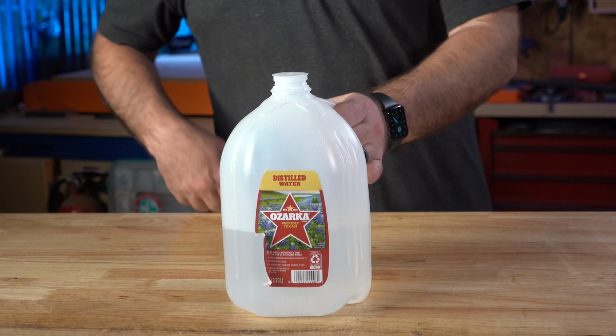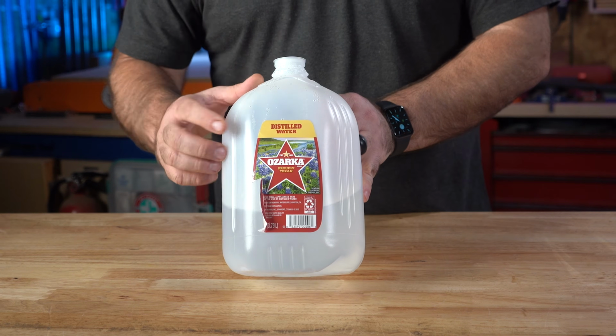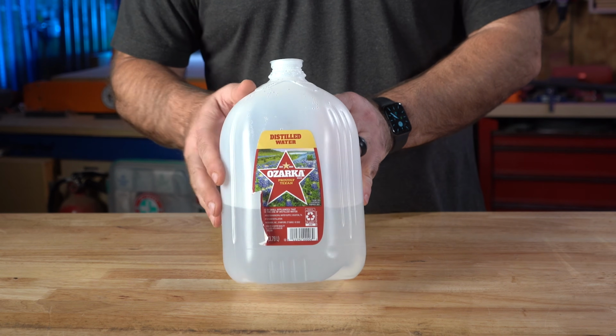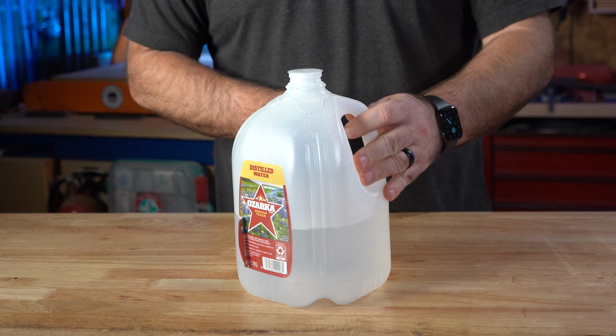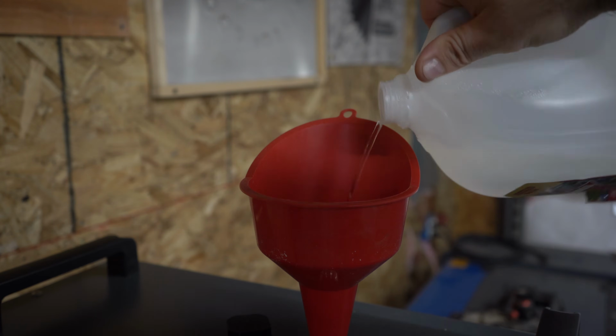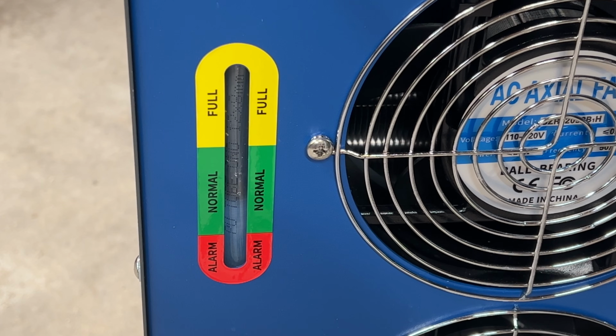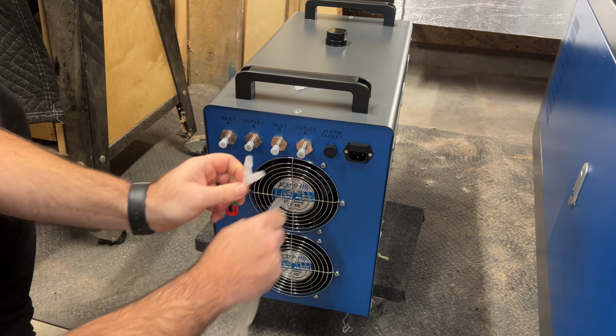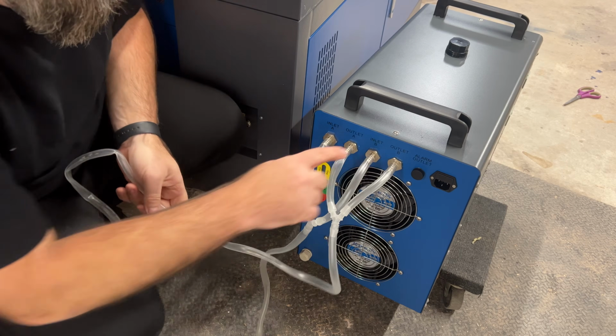With all of these systems, you'll want to use distilled water to prevent any corrosion in the system. It's really easy to get it all connected. You add the water until the level in the window reaches somewhere between the middle or top, to the normal or green area. You connect the water inlet to the laser outlet of the chiller.